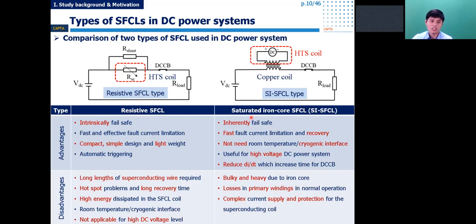Unlike the resistive SFCL, the saturated iron core SFCL uses the iron core properties to change the inductance to limit the fault. So the current does not directly flow through the superconducting coil, and no quench occurs. Therefore, the SI-SFCL is more suitable for high voltage and high capacity DC power systems.